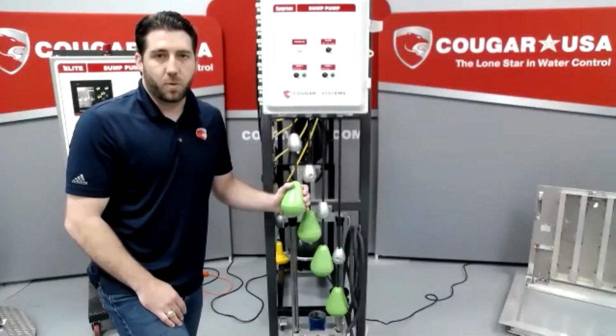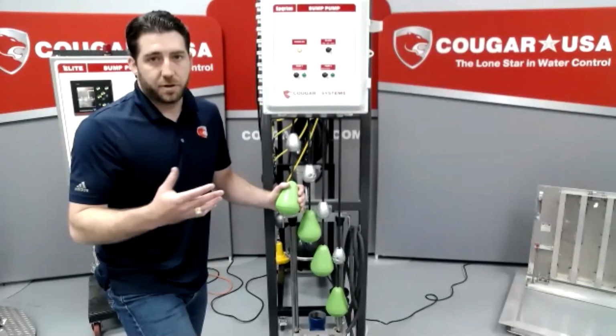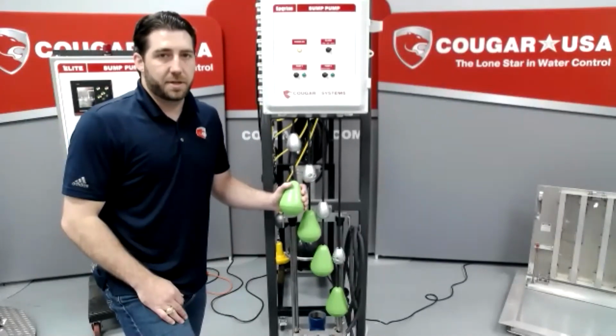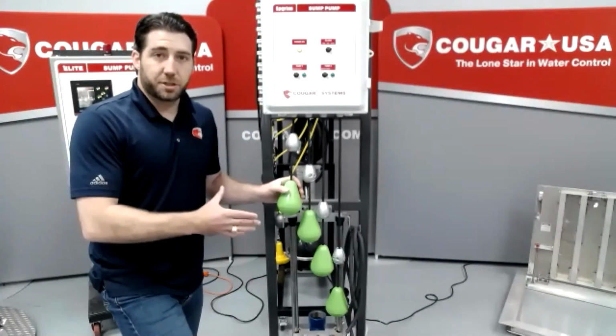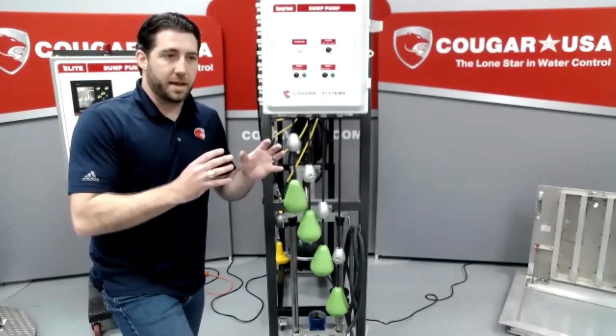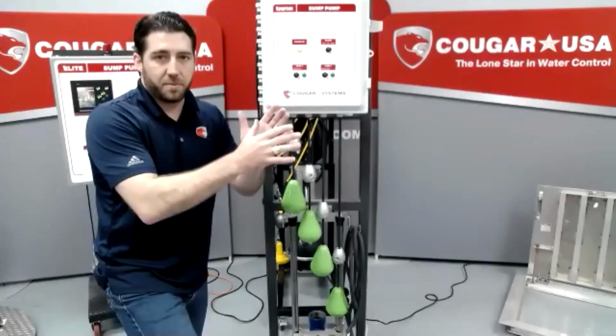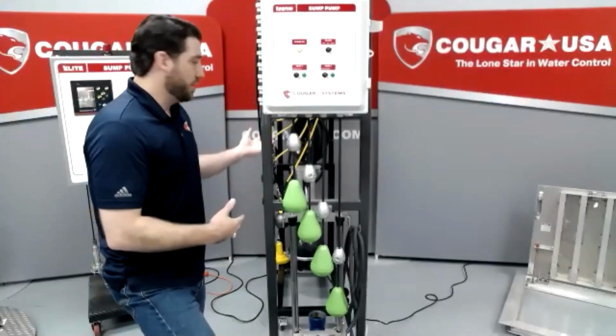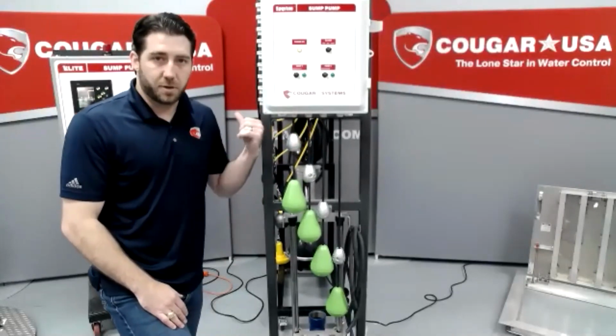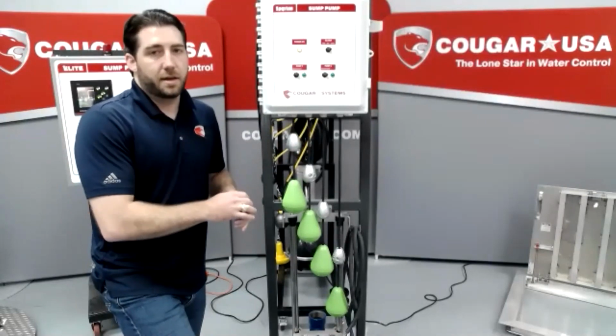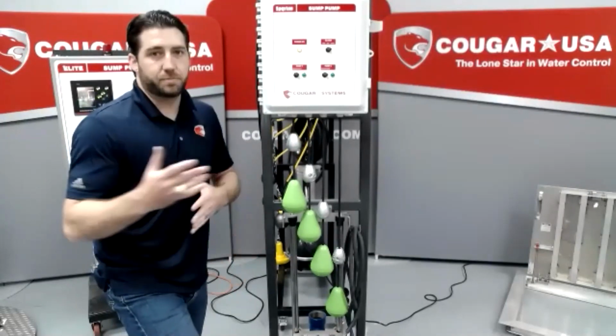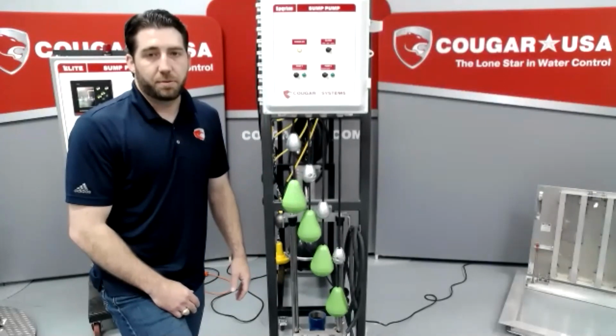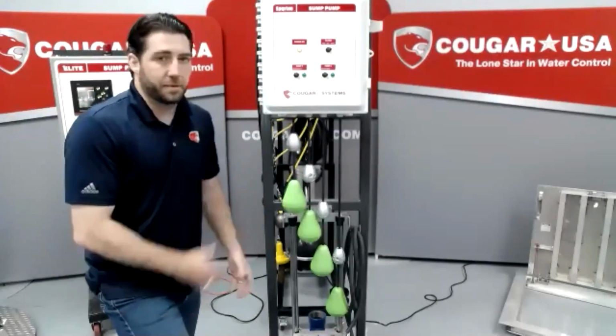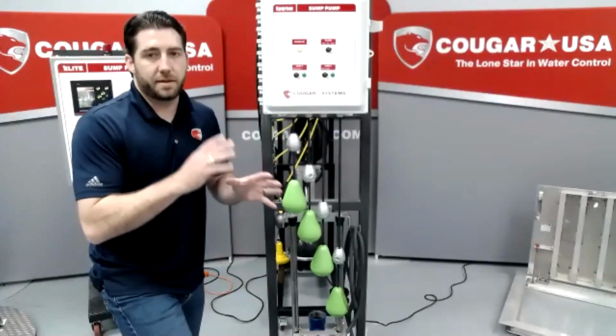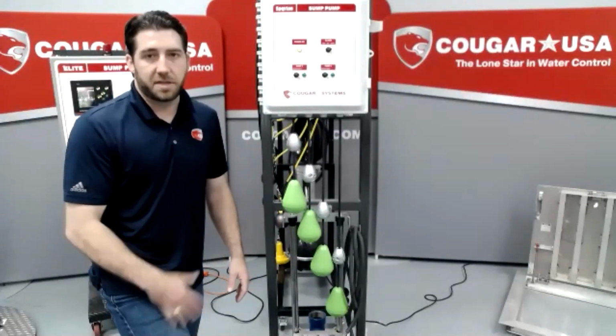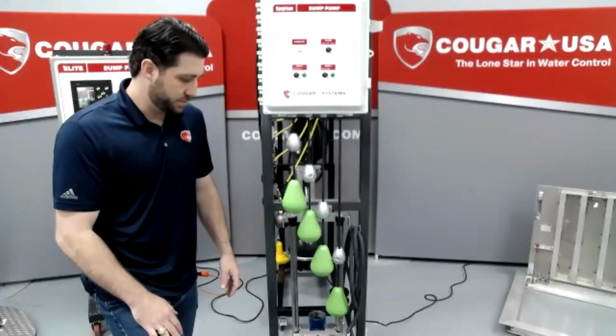You know, it's just going to require some additional coordination when you're initially running all of that wire, and I would definitely recommend having a junction box near the pit and then running regular wiring from there, and not trying to pull, you know, long distances of this SO cable through the conduit. It's just a mess initially, and it's basically impossible to ever replace it down the road. So I'd rather run regular cabling through the conduit and then have a junction box at the pit if you need to go longer distances. Okay.